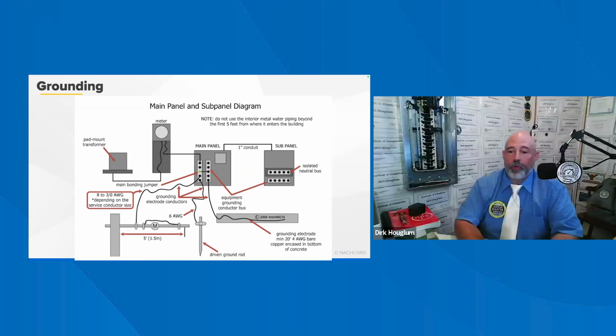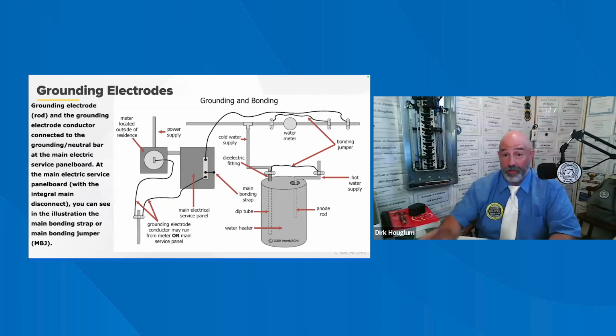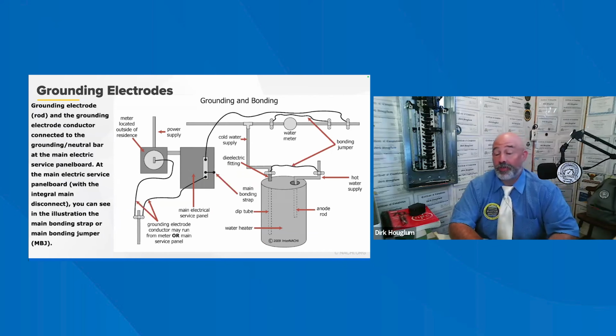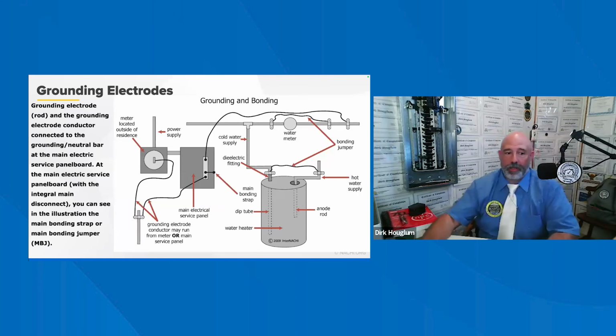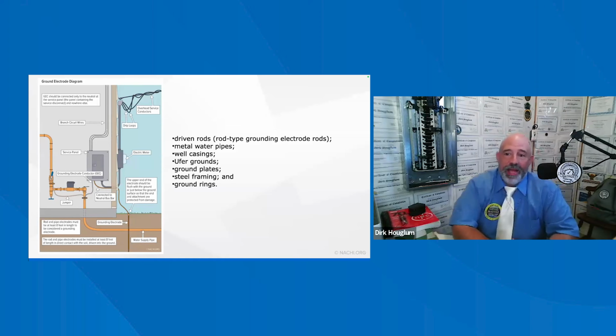This is critical for removing dangerous voltage imposed on the system via lightning strikes or overvoltage surges from high voltage on the power lines. It's very important to bond properly. Check out that video on bonding and grounding, Electricity 101. A grounding rod, footing reinforcing steel, and metal underground pipe are examples of grounding electrodes, which are metal electrically conductive terminals through which current enters the earth. There are several methods of connecting the grounding system to the ground, with the driven grounding rod being the most common in most areas.